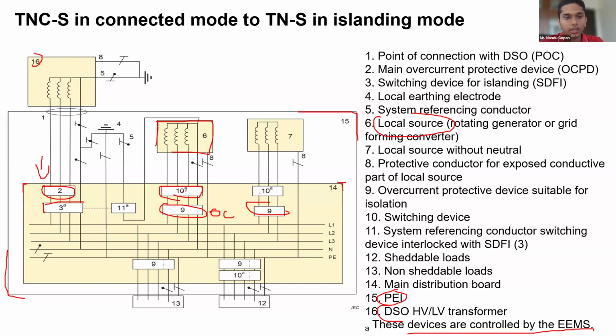Now the most important point in this is this part. This is where the changeover happens. You can read over here 11 and 3. 3 is a switching device for islanding, which you can shortly call SDFI. So 3 is a switching device for islanding mode. And 11 is a system referencing conductor switching device interlocked with SDFI. Meaning 11 and 3 are interlocked. So if one is on, the other will be off. If the other is off, the first one will be on. Both are switching devices, and obviously these two are also controlled by the energy management system. So this is how it will look in an overview.